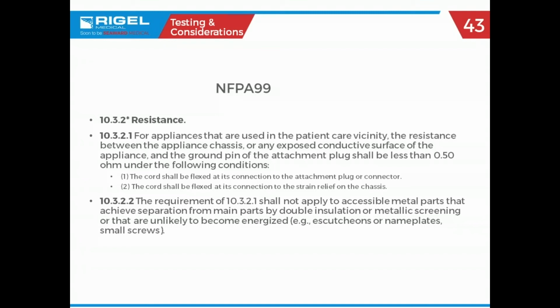Fact of the matter is, once equipment is out in the market for a while, you could have some film resistance building up, you could have some oxidation building up. So they've allowed a longer or a wider area for acceptance. So we can have 0.5 ohms, which you end up changing out a lot more line cords if you really follow that. Now this one's good. I mean, this is pretty new.